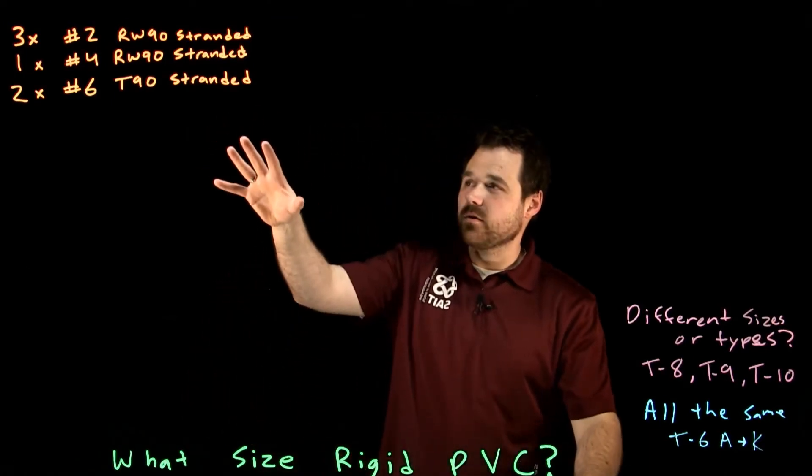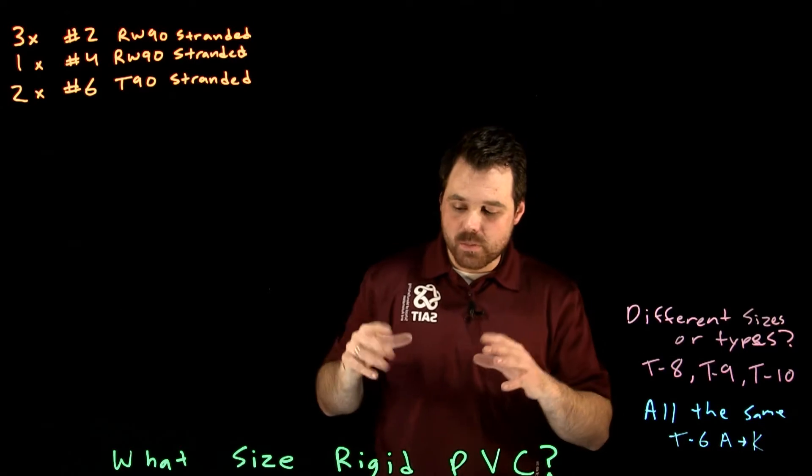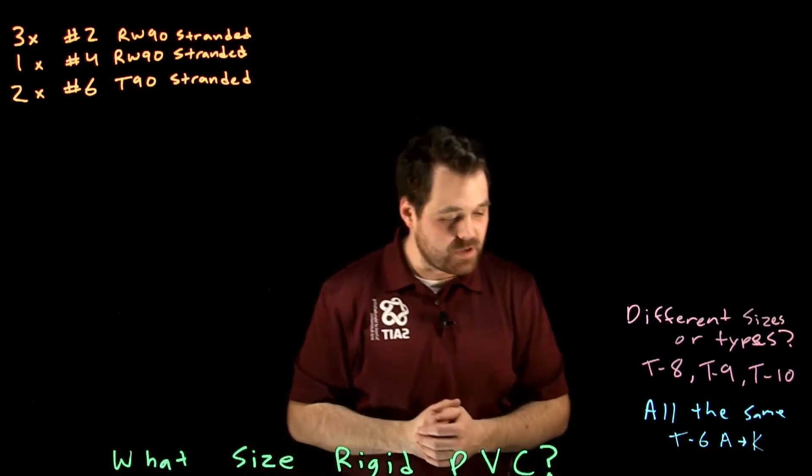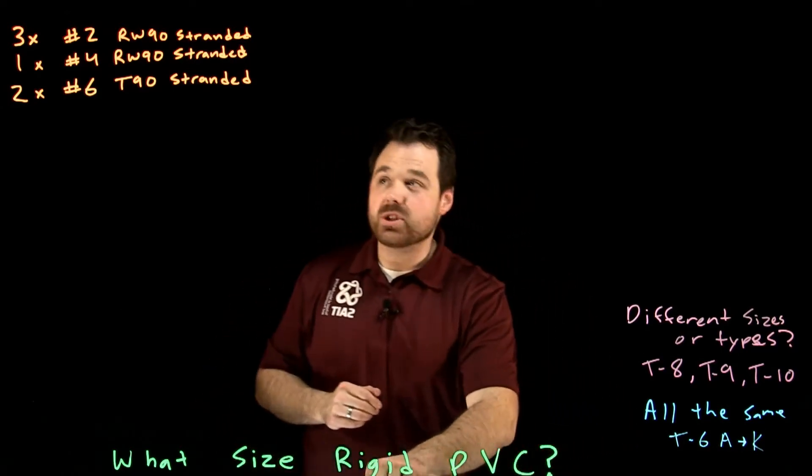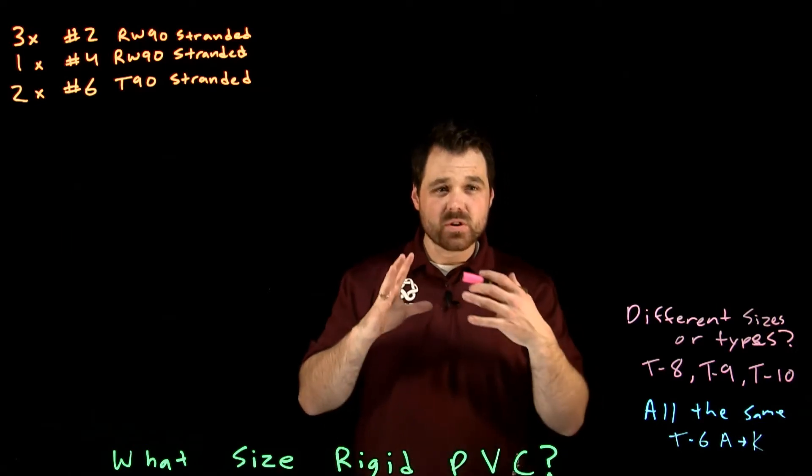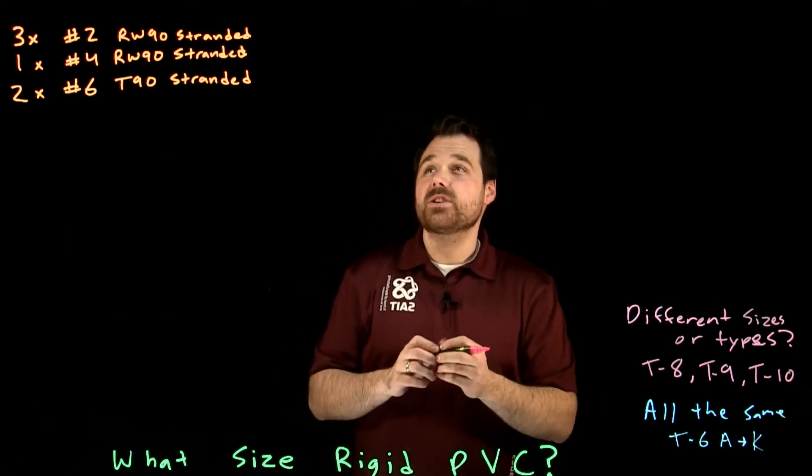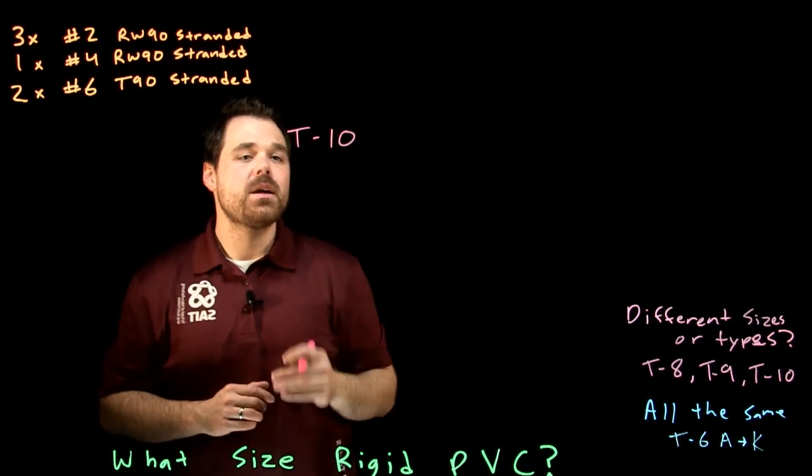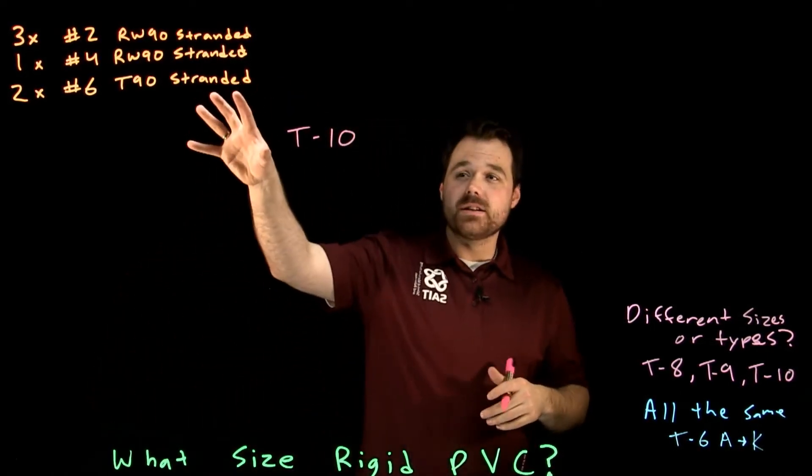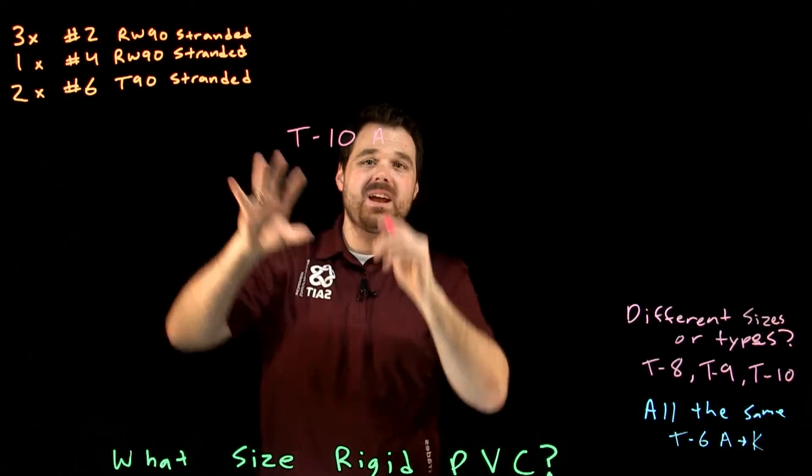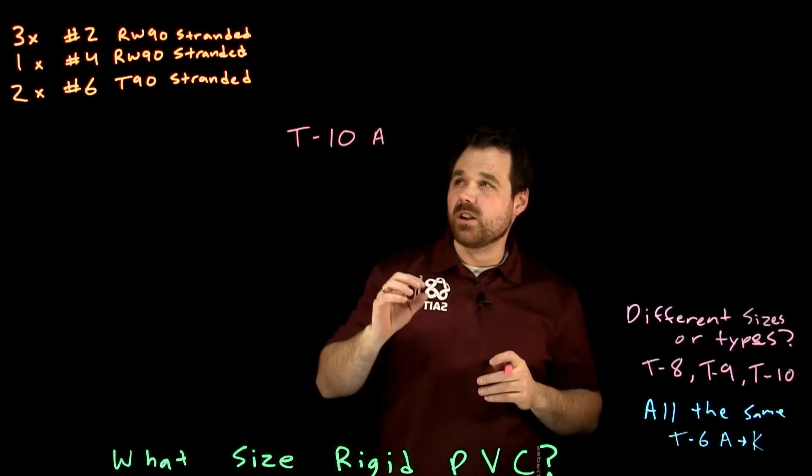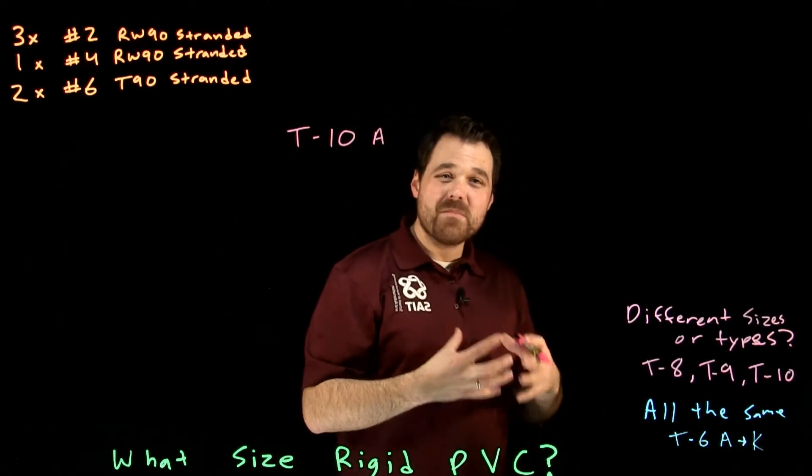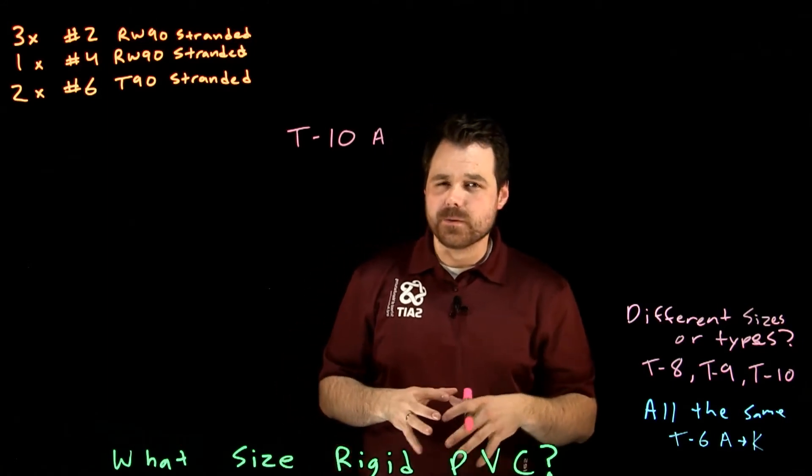So because we're using these different types of conductors, pulling it into a conduit, we want to figure out the rigid PVC for these guys. We have a couple steps we're going to follow. So first what we want to do is we actually first we need to go to table ten. Because these are stranded conductors, we're actually going to go to table ten A.